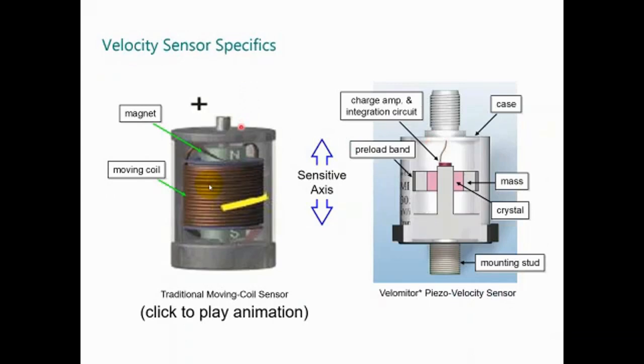The velocity. There are two different designs. The moving coil - you have a magnet and you have a coil. The coil is mounted on springs. When the machine vibrates, there's relative motion between the magnet and the moving coil, and it induces electromagnetic force. The electromagnetic force is called voltage, and the voltage is proportional to the velocity of vibration.